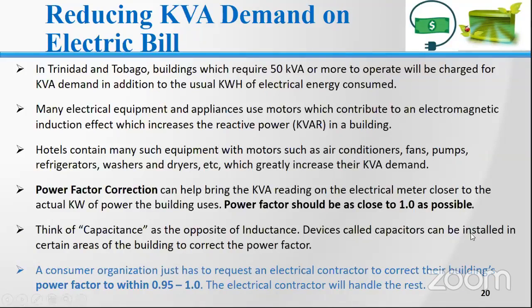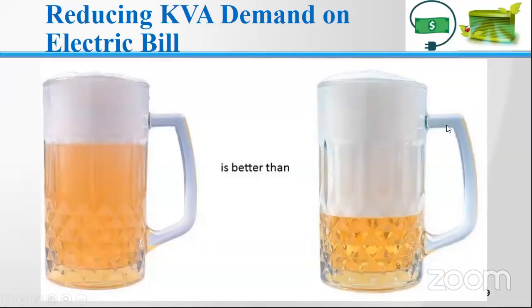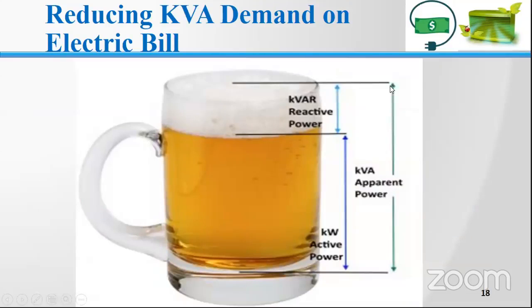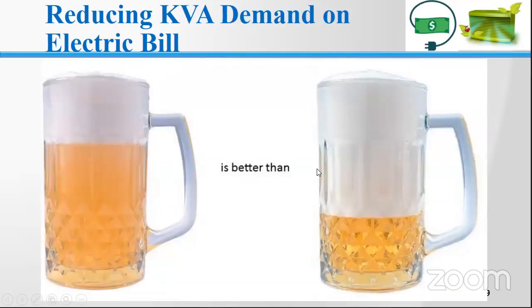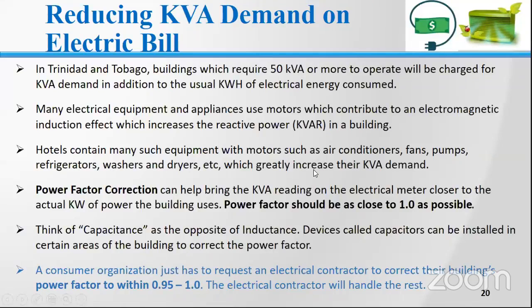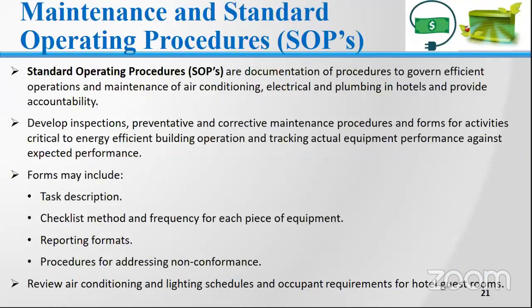Once they do this for you by installing devices called capacitors, these devices remove the reactive power, and you end up being billed for a kVA that is very close to the actual power you use, nothing more. I think for hotels, power factor correction is maybe more important than for most other businesses, because of the amount of air conditioners, fans, pumps, and refrigerators a hotel uses compared to other types of businesses. So I'd say power factor correction is likely needed by hotels more than most other organizations.